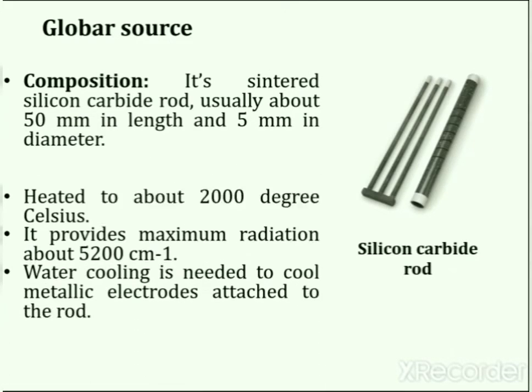The Globar source is composed of a rod of silicon carbide, usually about 50 mm in length and 5 mm in diameter. When this rod is heated to about 2000°C it provides radiation, with maximum radiation within the range of about 5200 cm⁻¹. The power consumption is normally higher than that of the Nernst Glower, and water cooling is needed to cool the metallic electrodes attached to the rod. The Globar source is less convenient to use, more expensive, and less intense than the Nernst Glower.